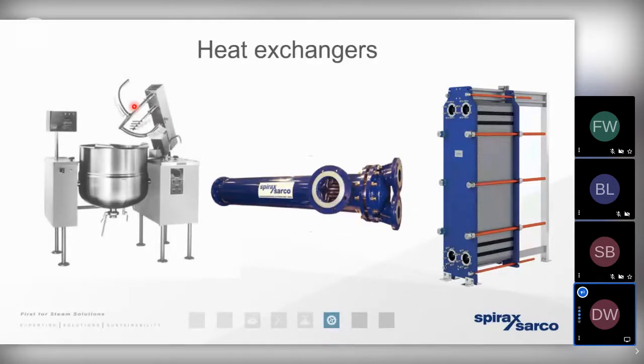So it bears mentioning that steam can be used for direct injection purposes, in which case the steam, and therefore the condensate as well, becomes consumed by the process or by the atmosphere. So when that's the case, there simply isn't going to be any condensate to remove anyway. The condensate and the sensible heat become part of the process. So an example of a closed loop system could be a jacketed vessel, a shell and tube heat exchanger, or even a plate heat exchanger.